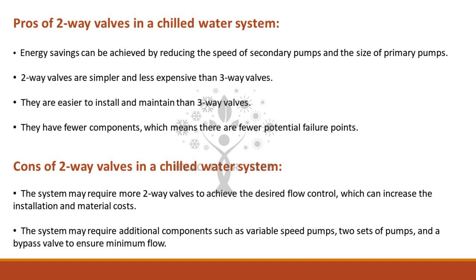Pros of two-way valves in a chilled water system: energy savings can be achieved by reducing the speed of secondary pumps and the size of primary pumps. Two-way valves are simpler and less expensive than three-way valves, easier to install and maintain, and they have fewer components, which means there are fewer potential failure points.